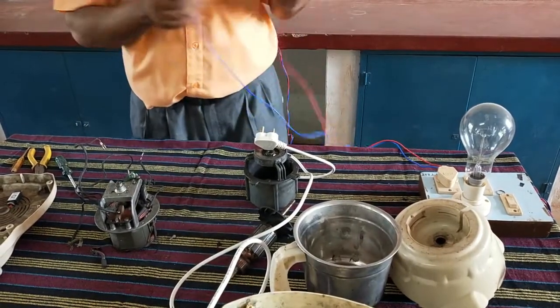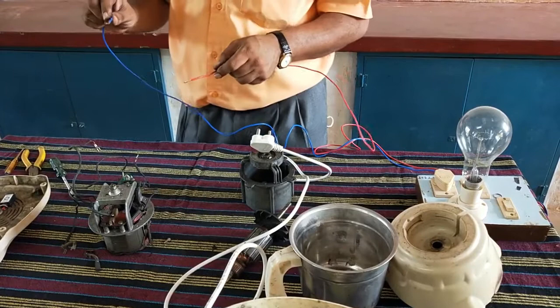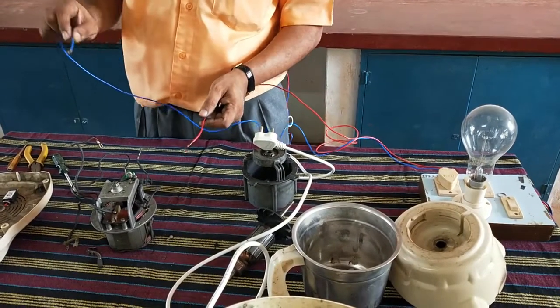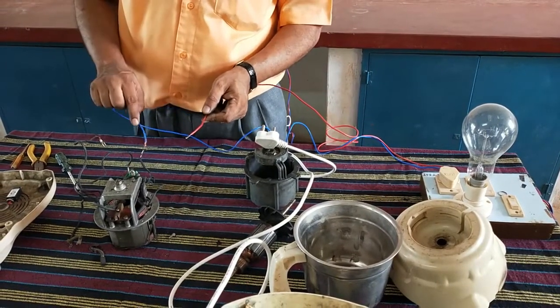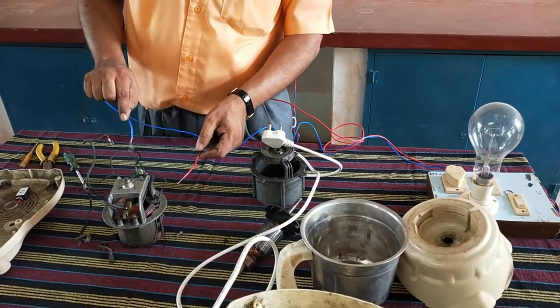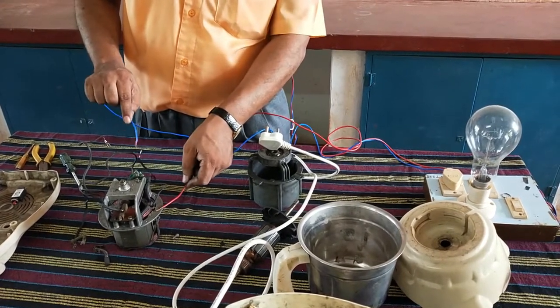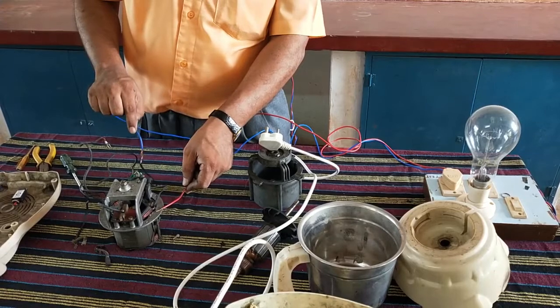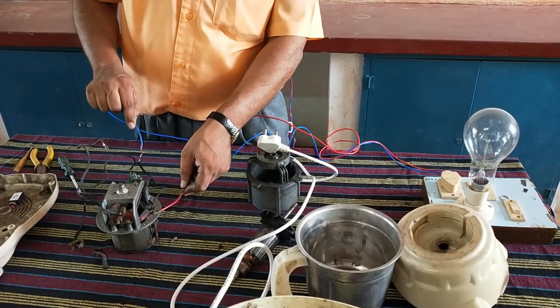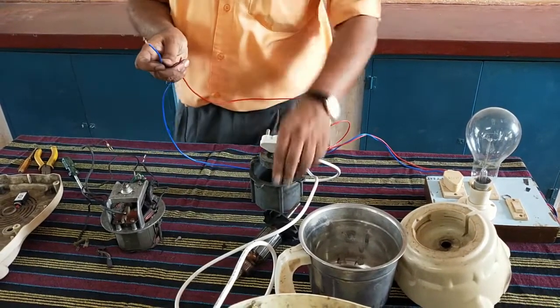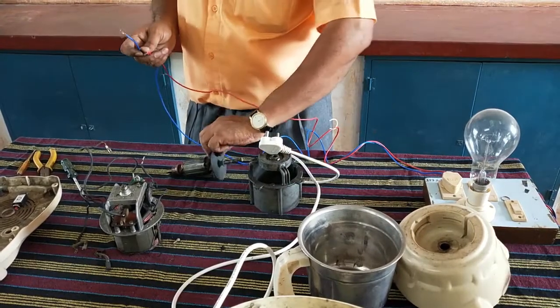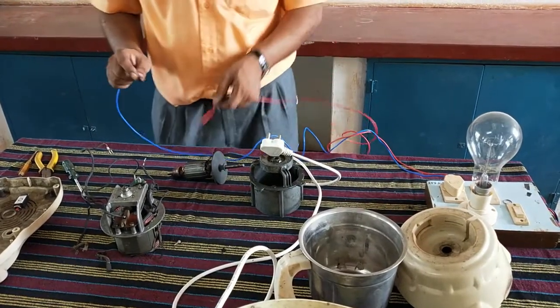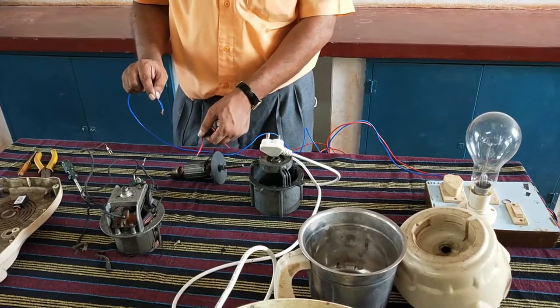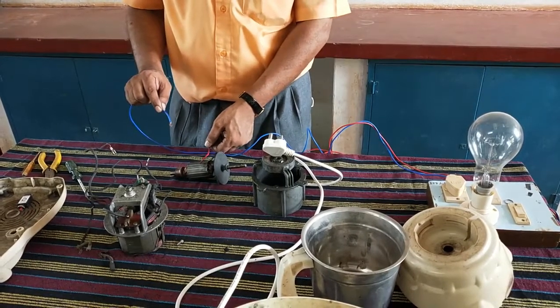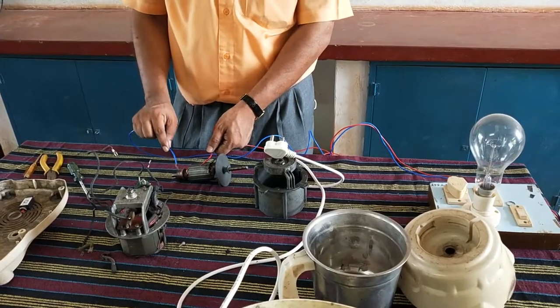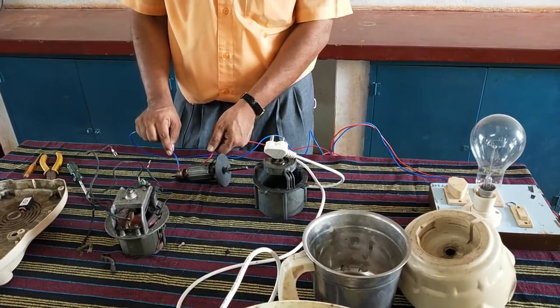Now check for an earth fault or leakage. So connect one terminal to the coil and the other to the body. So there is no leakage. Similarly, you can check the earth leakage in the armature also. For that, connect the one terminal of the test lamp to the body and the other to the commutator. So there is no leakage.